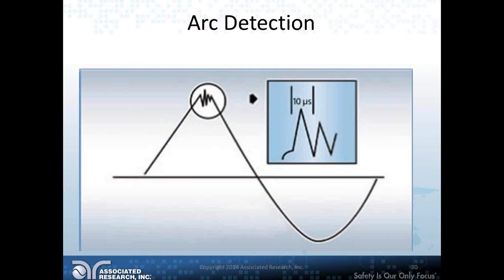High-impedance arcs and corona generate high-frequency pulses that ride on the low-frequency test current waveform. These pulses may have a frequency ranging from less than 30 kilohertz to more than 1 megahertz and can be very short in duration — often less than 10 microseconds — which is why arcing is called a momentary discharge.